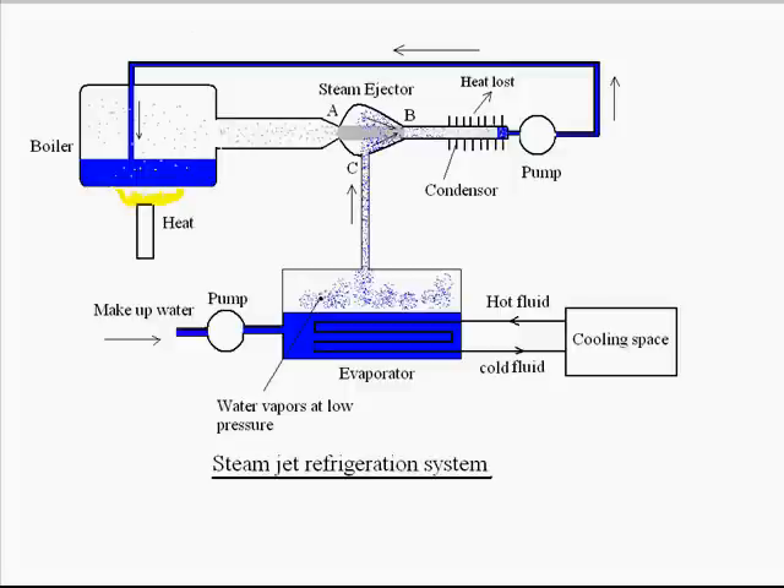Now, in the evaporator, water is evaporating continuously, meaning there is a loss of some water because water is evaporating and entraining with the steam jet and ultimately going inside the boiler. To compensate for this, there is an extra pump providing makeup water to the evaporator. The water inside the evaporator is continuously chilling, and this chilling effect is used to cool the cooling load or the cooling space. We can see a heat exchanger has been applied — a hot fluid enters inside, passing through the evaporator vessel through the liquid water.